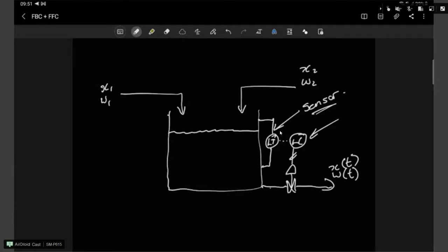Now, in terms of the thermostat, where that serves as the controller as well, it's got some form of a little knob or dial, and that just tensions that coil a bit more, or less, to determine the temperature at which it can make a contact or disengage that contact. It's obviously not 100% perfect because it's got a bit of a range, so it will engage only at, let's say, 45 degrees if the set point is 50, and it will engage at the temperature of 45 and disengage, let's say, at a temperature of 55, depending on the quality of materials used and the accuracy of that instrument.